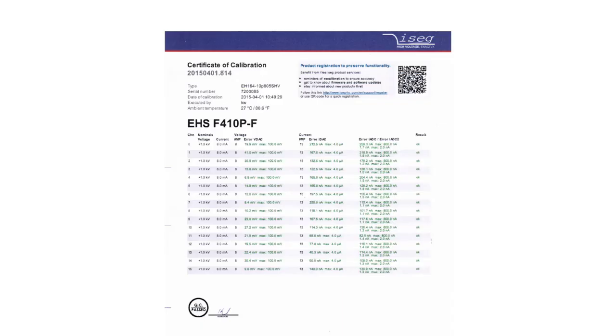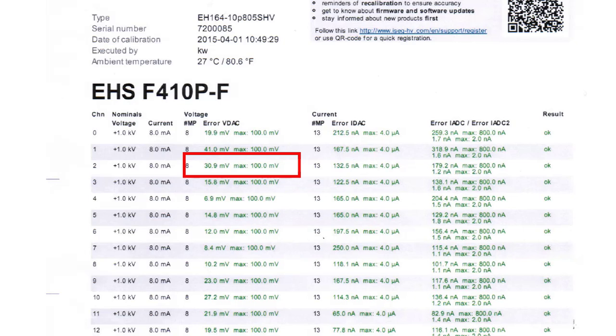This is the calibration report for the module used in the previous measurements. The module has been calibrated 5 years ago. Still, the error we measured for channel 2 corresponds precisely to the error given here.